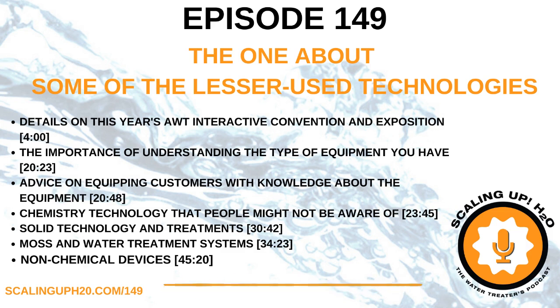The neat thing is, not only can you look at the conductivity of the water, you can look at the water meter readings. You can install sensors that actually measure PTSA, which is the amount of treatment that's actually in the system. By measuring the PTSA, you know how much product you have recirculating in the water. You may use an ORP controller to determine your oxidant demand, and that will basically turn on and off a chlorine pump that helps control your biological needs. So controllers are very smart these days, and they're doing real-time adjustments as we're there.